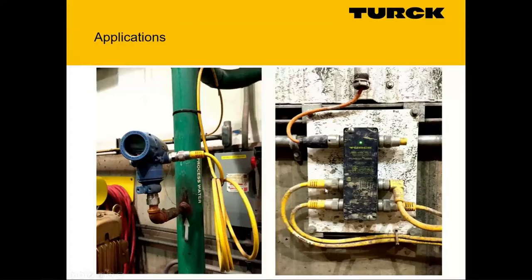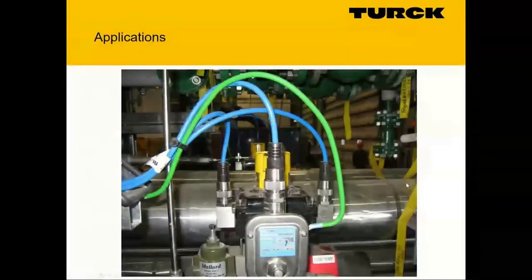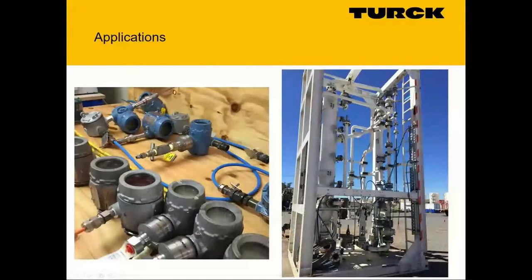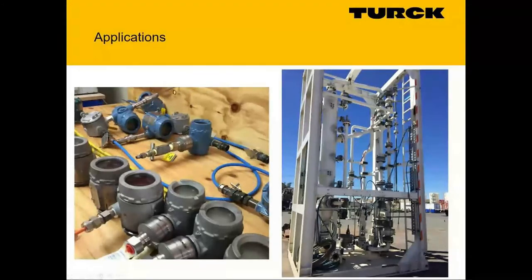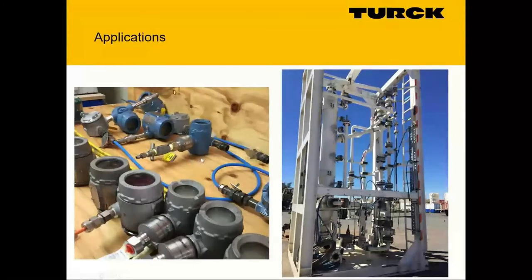Here's one I worked on extensively in Australia for Turck — offshore equipment where the customer was making his own connectors on his instruments and getting frustrated because they just weren't working. Everything he picked up to show me was loose — nothing was sealed, nothing was watertight. We replaced it all with the same product I use with everybody else, and the problem went away.